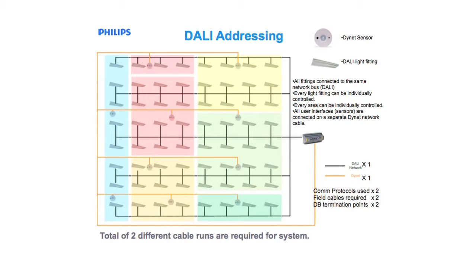DALI addressing connects each of the ballasts together into the same network. The DALI system allows for each group of lights to be controlled separately. The sensors still require their own network to communicate area status information to the load controller. This system still requires 2 networks to be run. These networks are often running in parallel with each other.